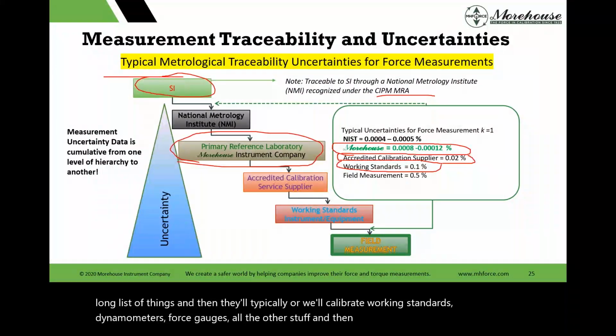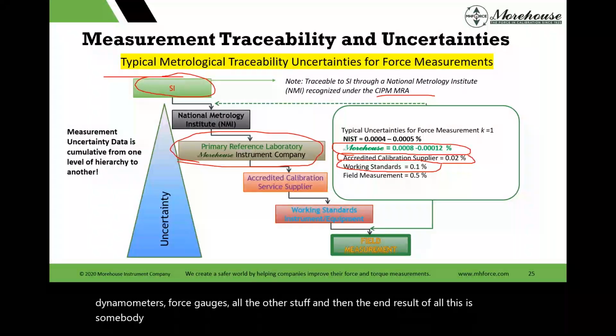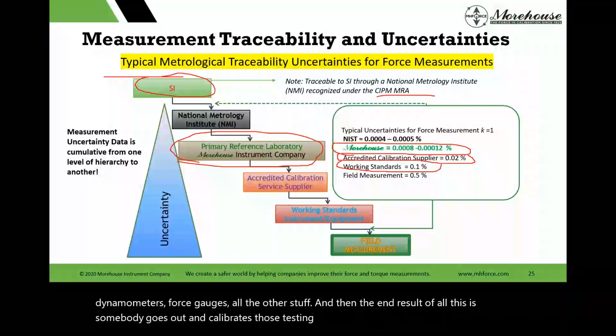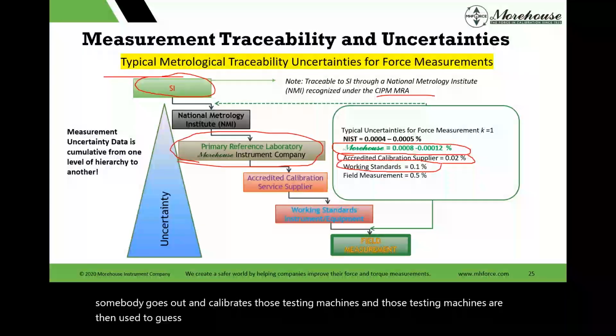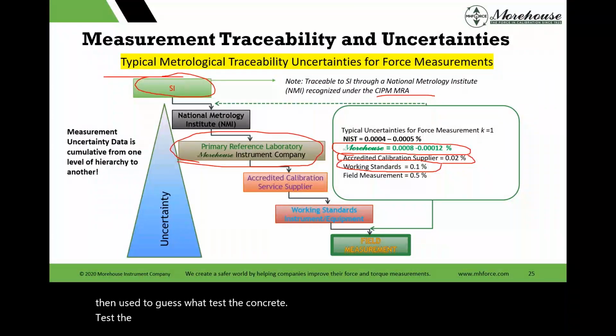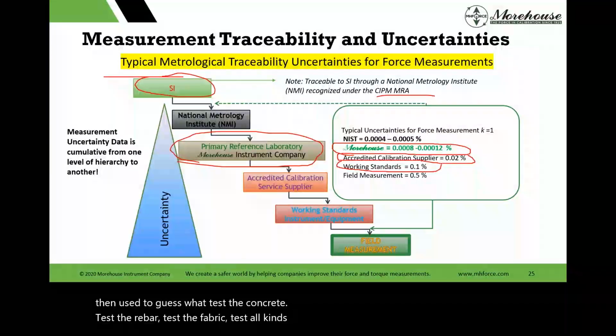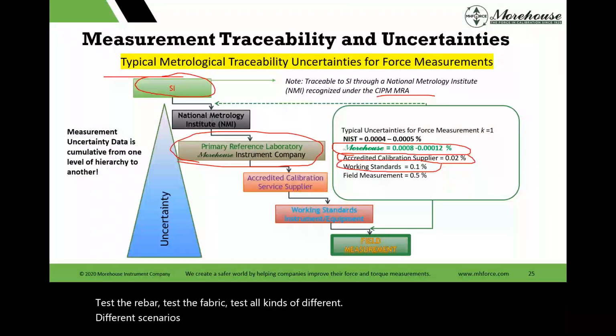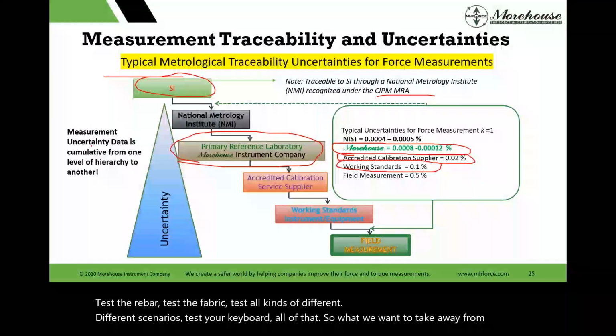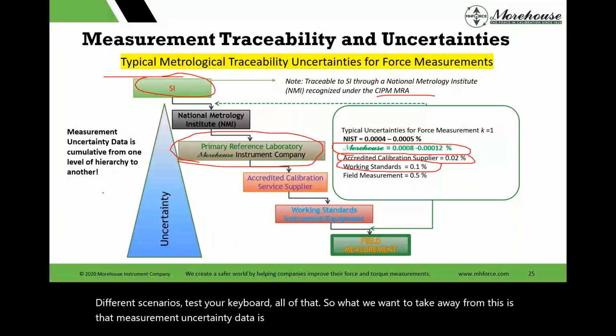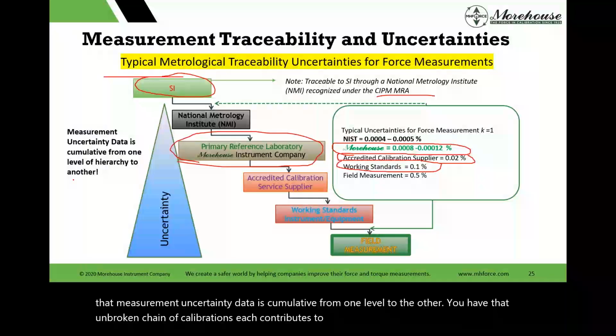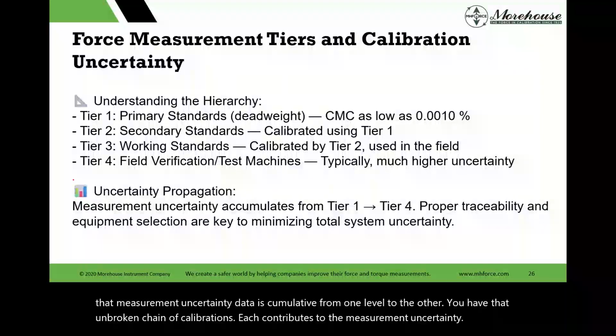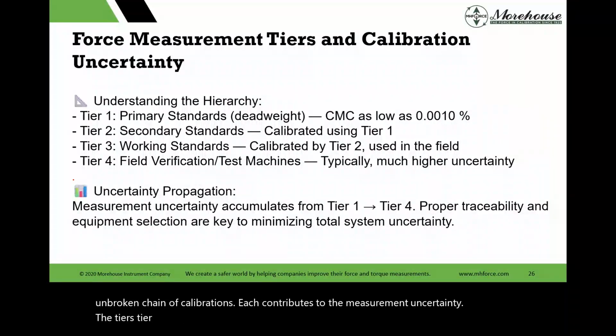And then the end result of all this is somebody goes out and calibrates those testing machines, and those testing machines are then used to, guess what? Test the concrete, test the rebar, test the fabric, test all kinds of different scenarios, test your keyboard, all of that. So what we want to take away from this is that measurement uncertainty is cumulative from one level to the other. You have that unbroken chain of calibrations, each contributes to the measurement uncertainty. The tiers: tier 1 primary standards, tier 2 secondary standards, tier 3 working standards, and then the test machines.